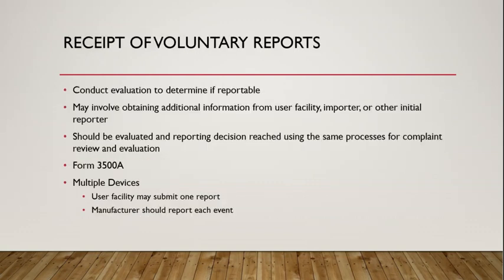There will be instances where voluntary reports are involved, and if so, they need to be evaluated to determine if they're reportable, and additional information may need to be obtained. When it's all gathered, it should be evaluated and the decision made just the same way you would for a complaint. And there's the form and the rule on when it happens with multiple devices. The user submits one and the manufacturer should submit also.